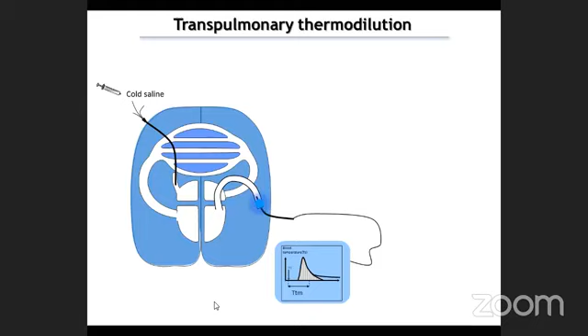How does transpulmonary thermodilution work? Patients need to be equipped with a central venous catheter in the superior vena cava territory, if possible, and with a femoral arterial catheter. The thermodilution measurement is performed by injecting cold saline through the central venous catheter. The decrease in blood temperature is then detected by the arterial catheter, and the thermodilution curve is obtained. And this is the mathematical analysis of the thermodilution curve, which provides intermittent cardiac output calculation. Transpulmonary thermodilution is an accurate and precise method, but it only provides intermittent cardiac output measurement.